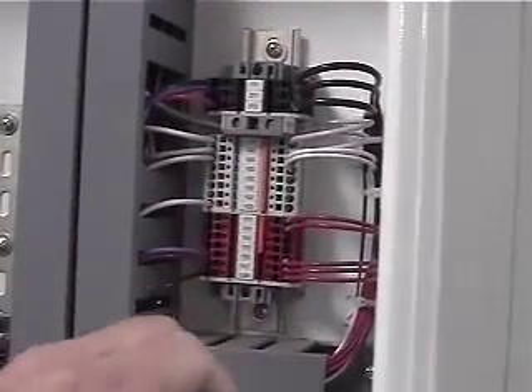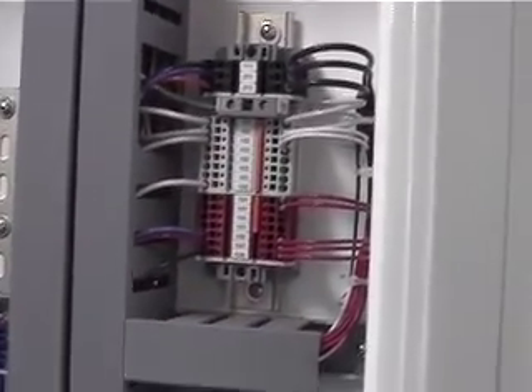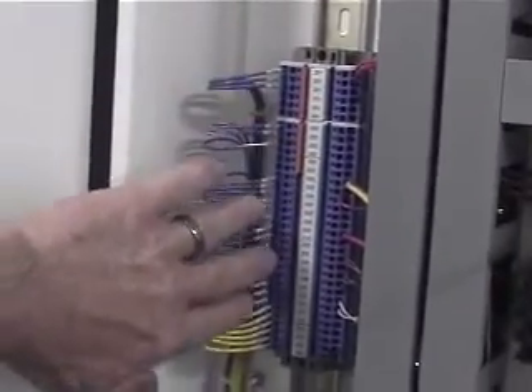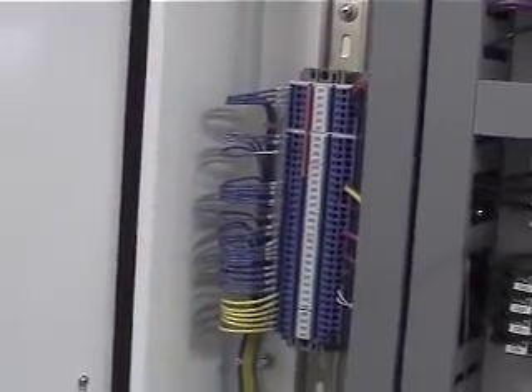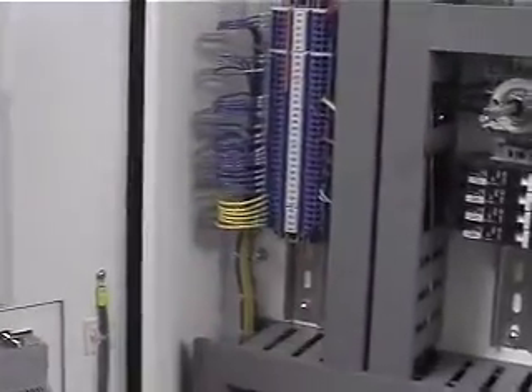In our wiring configuration, red 101 is control voltage. When I say high voltage, it's 120 volts. Anything in blue is low voltage, either 24 VDC that originates from here, or your RTDs, your temperature sensors. The yellow: NFPA and UL both say if you don't know what the voltage is, you have to make it yellow.